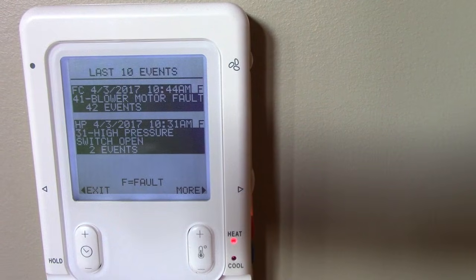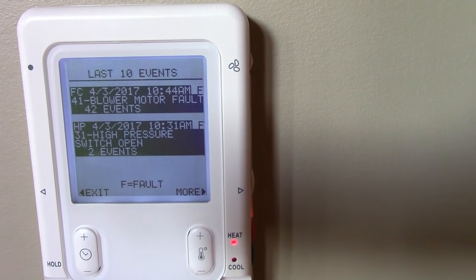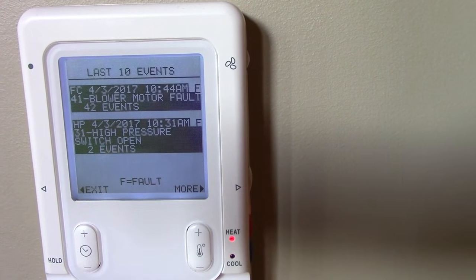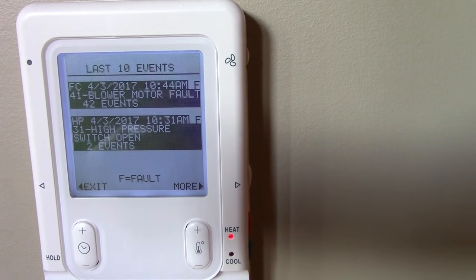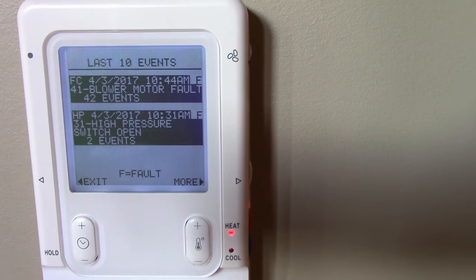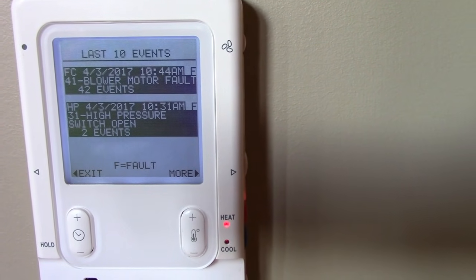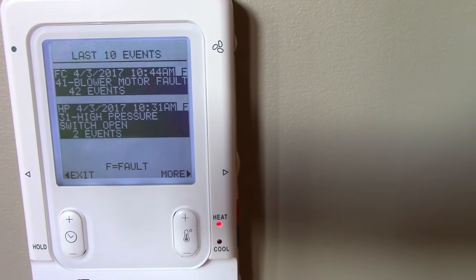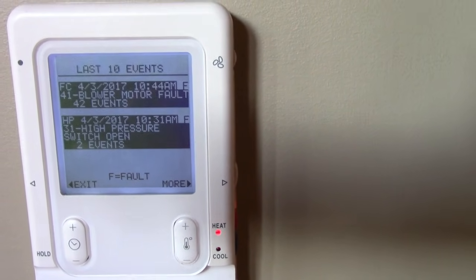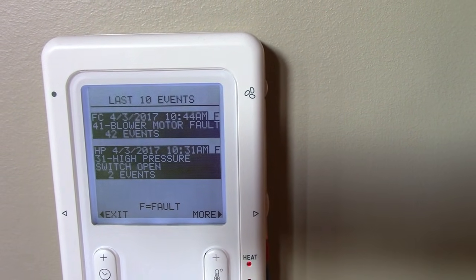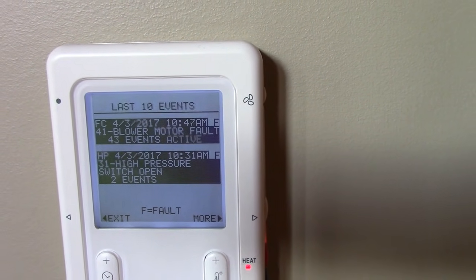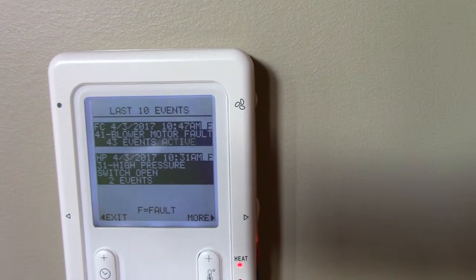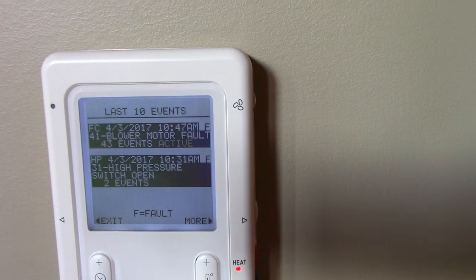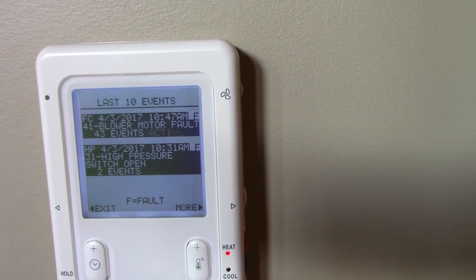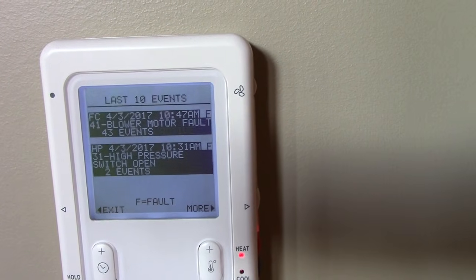So, just going by the thermostat here in its diagnostics, we've got two faults. The first one that's showing up is an error 41 blower motor fault, and the one after it is a high pressure switch open. I'm guessing the high pressure switch one is because the blower motor is not working. This is a heat pump, so there's no air flowing past the coils down in the furnace, or air handling unit if you want to call it that. It's tripped the high pressure switch as well. Obviously the motor one is active right now, it's flashing. Now we get to start tearing it apart and finding out what's going on.